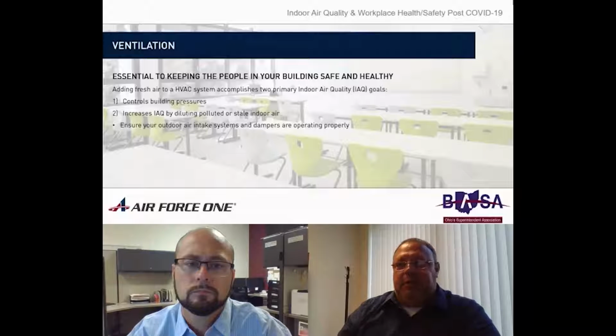That's a good idea, with the exception that a lot of times your equipment cannot handle the extra outdoor air, especially on your really hot and humid days or your really cool days. So it starts causing trouble in your space. The other big one is it can make your operating costs double on the HVAC side of things. So it's very important to make sure ventilation is good, but not beyond the capabilities of your equipment. We'll go a little further into the ventilation side once we get to PHI, but I'll let Austin move on.